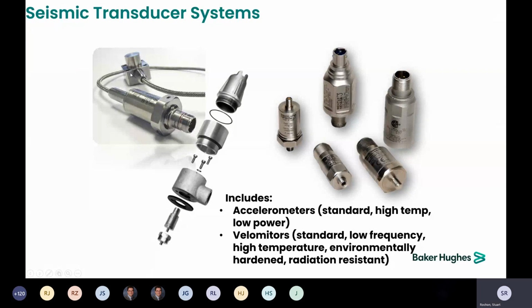Here we've got a picture of one of the shear mode type transducers. Generally, the piezoelectric component is housed separately, and then they use a mineral insulated hardline cable to go back to the electronics, just to get the electronics out of that high temperature so that they have a chance of surviving. Where this head might survive at 900 degrees plus, these electronics really need something under the 300 degree range.